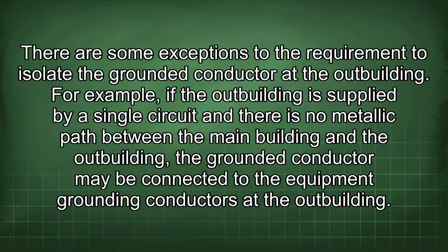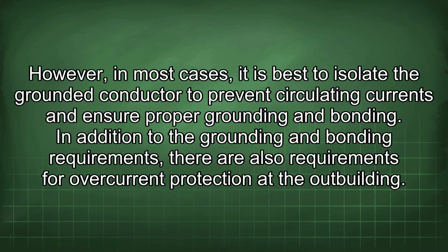For example, if the outbuilding is supplied by a single circuit and there is no metallic path between the main building and the outbuilding, the grounded conductor may be connected to the equipment grounding conductors at the outbuilding. However, in most cases, it is best to isolate the grounded conductor to prevent circulating currents and ensure proper grounding and bonding. In addition to the grounding and bonding requirements, there are also requirements for overcurrent protection at the outbuilding.